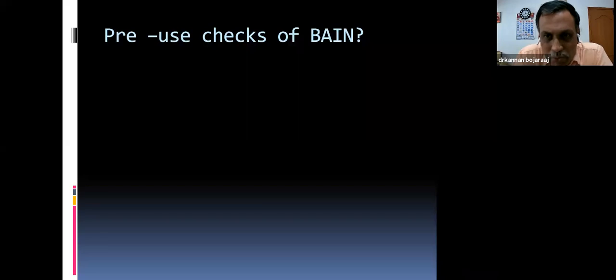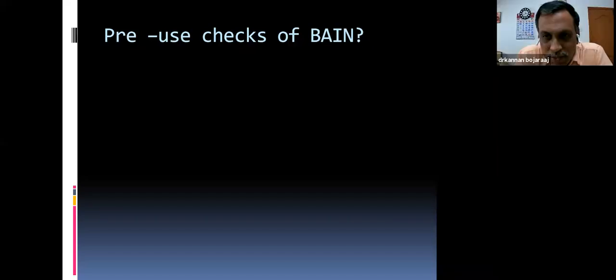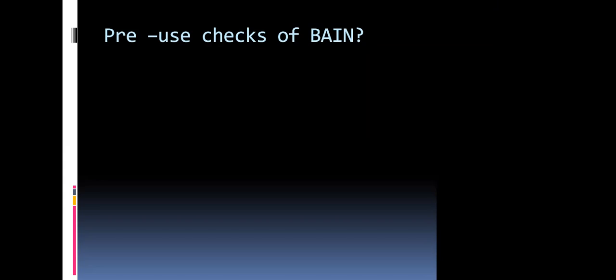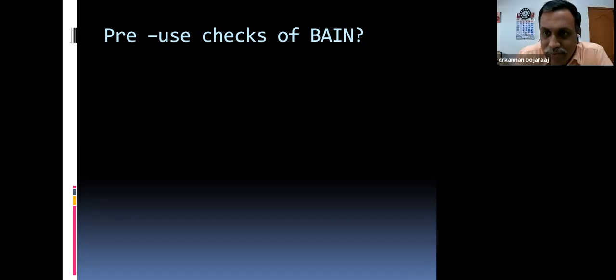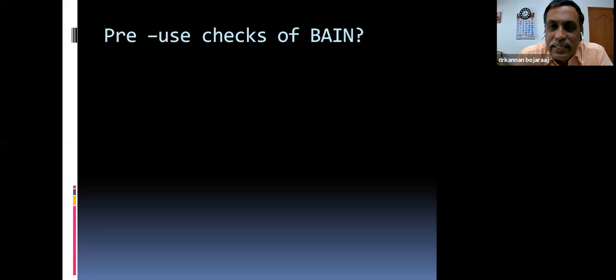You are occluding the tube. Sir, patient end. Patient end, you are occluded. Then we have to use oxygen flush, sir. After removing, if the inner tube is patent, due to the Venturi effect, the air will be sucked, so the bag will deflate, sir. The reservoir bag is collapsed. Yes, sir. Am I correct? Yes, okay.